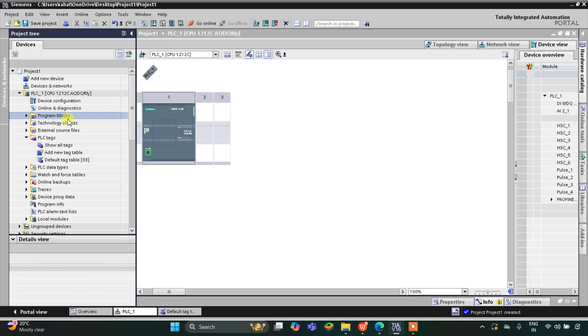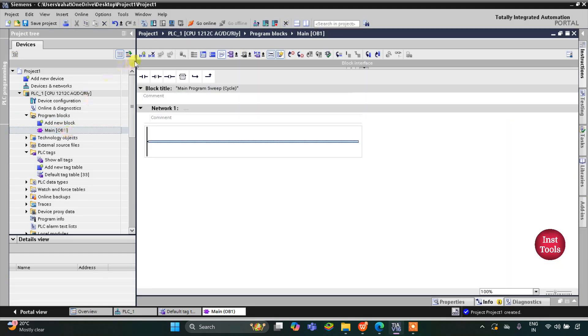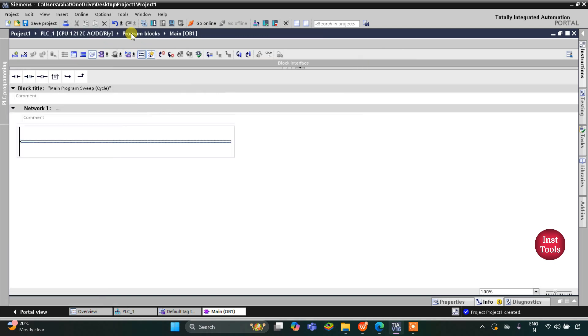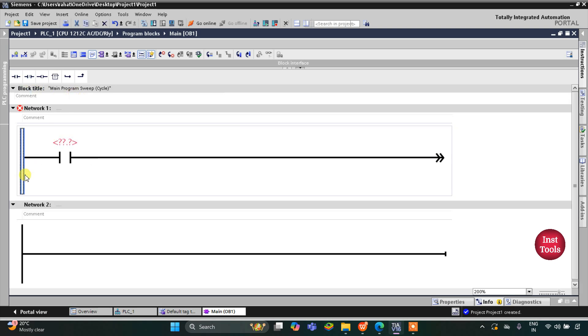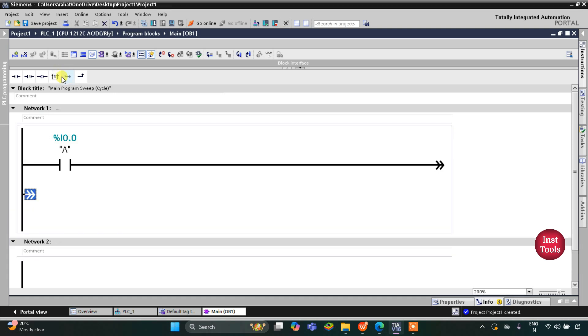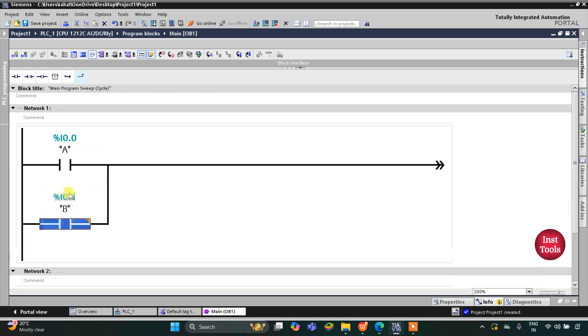Let's go to Program Blocks, Main OB1, where we will draw the ladder diagram. I will collapse and zoom in. First, I will insert a normally open contact for A. Then, since there is an OR logic gate between A and B, I will open a branch and add a normally open contact connected in parallel with A, implementing the OR logic gate.